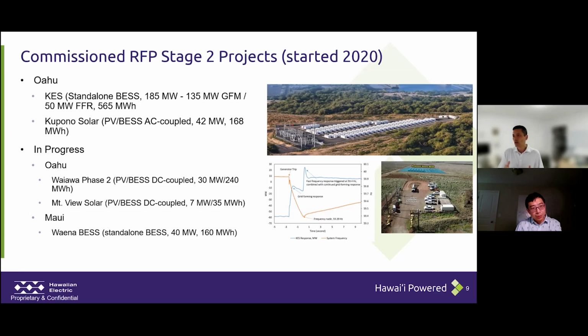So from 2020, even through now and into the future, all of our utility scale plants that come onto the system and include battery energy storage are also required to have grid forming controls. On Oahu, we added what we call KES, or Kapolei Energy Storage, shown in the picture on top. That's 185 megawatts of standalone BESS, including 135 megawatts of grid forming used for load shifting, and also 50 megawatts of FFR.